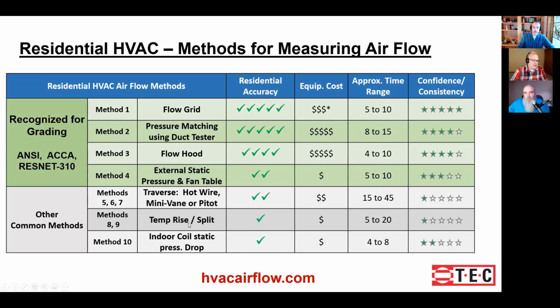and it doesn't work. This is a situation Jim Bergman tells about, somebody using MeasureQuick, and they said, I'm getting 4 tons out of a 3-ton system. Like, yeah, probably not. Yeah, exactly. Where's your probe? It's too close to the evaporator coil.